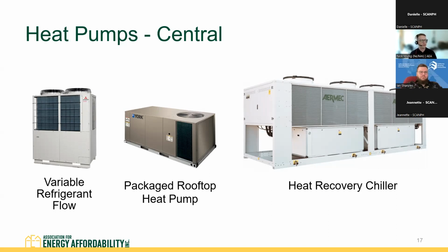There are also packaged rooftop heat pump units for common areas or community rooms, hallways, and things, as well as heat recovery chillers. You can do 4-pipe hot water and chilled water systems with heat pumps—so if you have buildings with a hot water loop and a chilled water loop for heating and cooling, you can do that with a heat pump. You don't need the boiler-chiller combo; you can do it all with a heat recovery chiller, getting it all in one system.